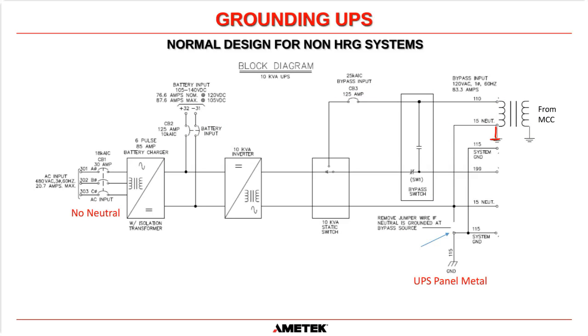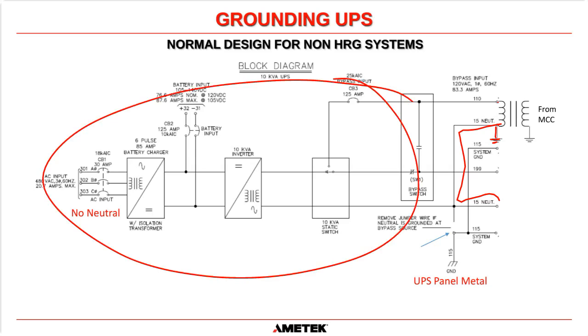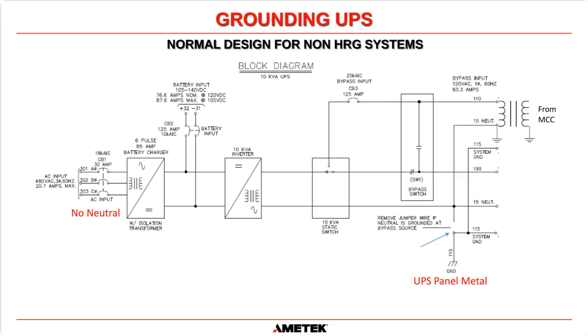And what tying this ground point to the neutral within the bypass transformer does is it allows us to put the system in bypass and still have the neutral connected to ground while we replace the whole UPS. In most cases, we do have to get into our MBSs, an external MBS, to make it absolutely safe, but that's the intention. So when you do connect the secondary of this transformer to ground within the transformer itself, you then have to go into the UPS and remove the jumper wire. As it says here, remove jumper wire if neutral is grounded at bypass source.